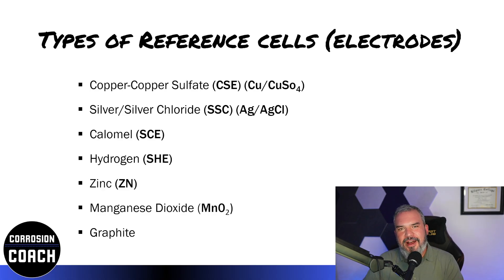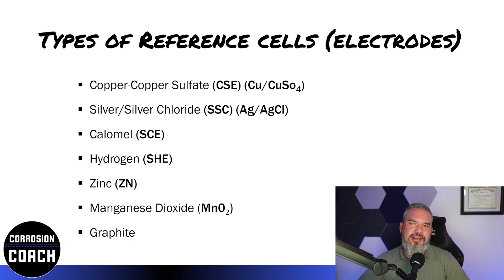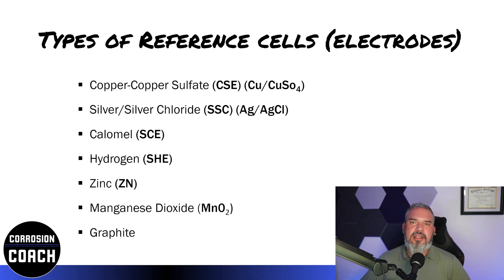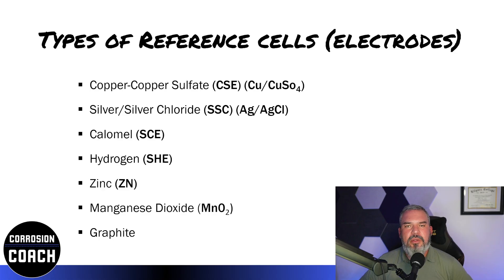The one at the top is the one we use most out in the field. If you're on land, that's probably what you're using — a copper-copper sulfate reference electrode, or CSE. It's very commonly used on land. However, we can't use it in certain applications — for example, in seawater. That high chloride content can penetrate the porous tip of our electrode, contaminate it, and make your readings inaccurate. So we can't use it in saltwater environments.